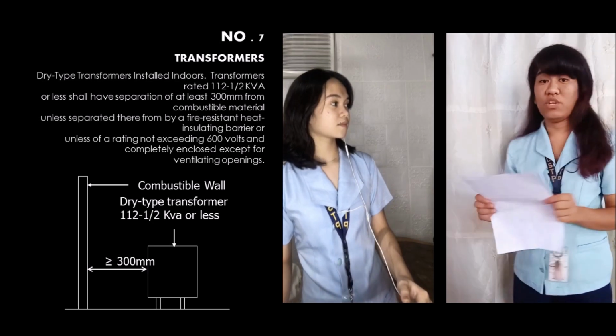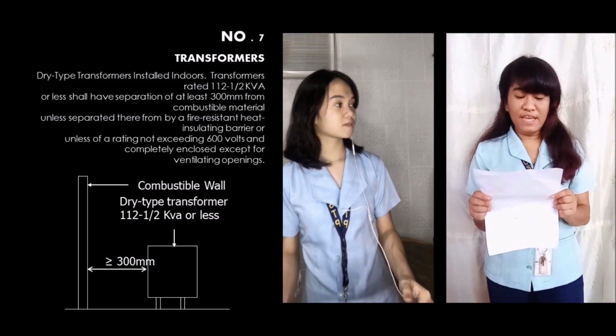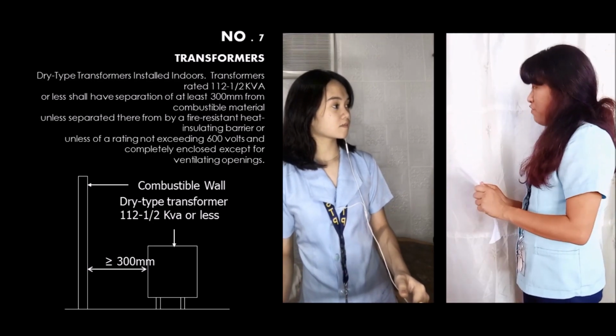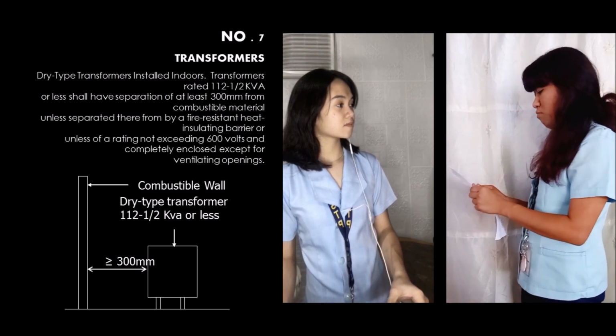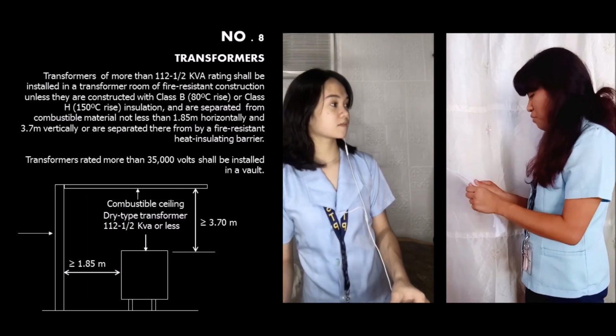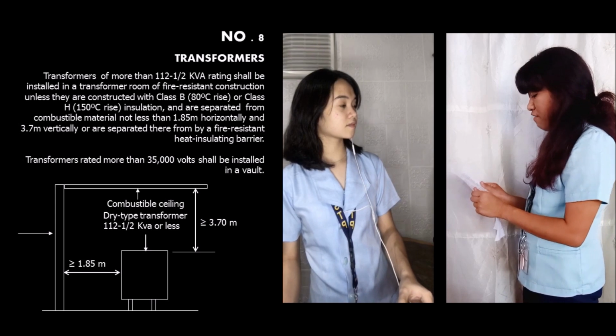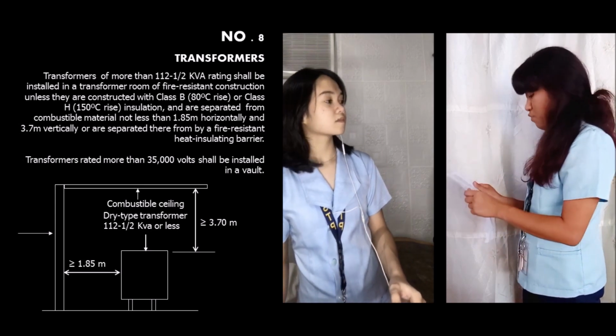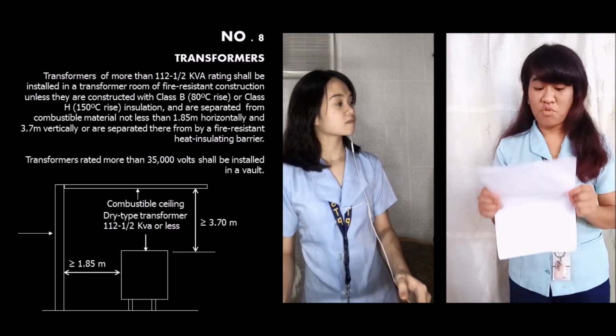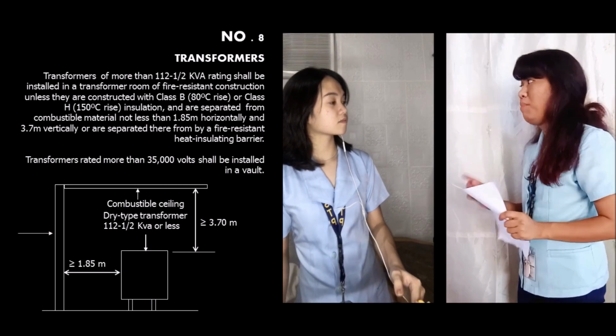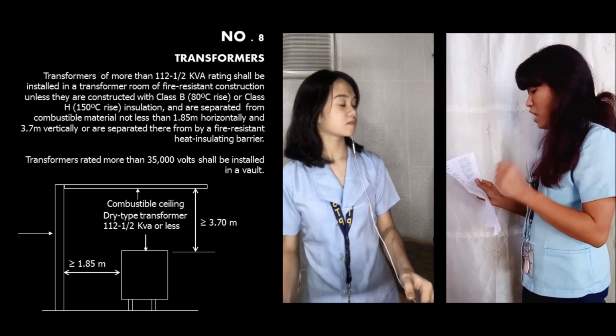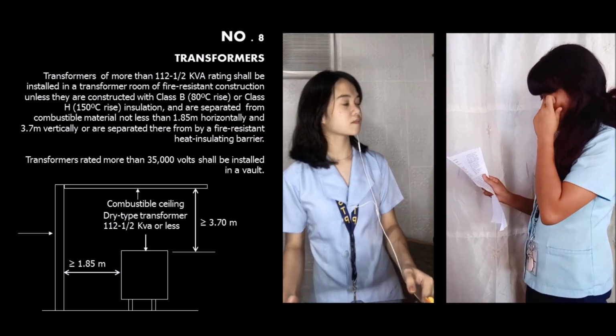Dry-type transformers rated 112-1/2 kVA or less shall have a separation of at least 300 mm from combustible materials. Transformers of more than 112-1/2 kVA rating shall be installed in a transformer room and are separated from combustible materials not less than 1.85 meters horizontally and 3.7 meters vertically.